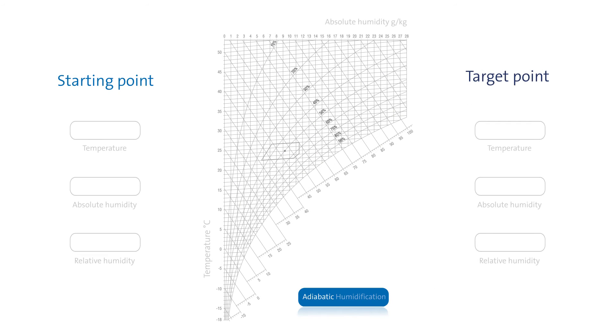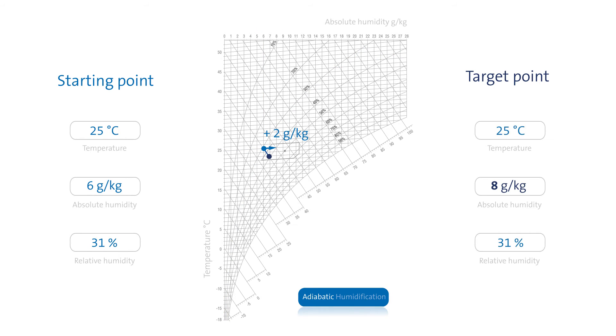An HX diagram can be used to illustrate this process. As a result, adiabatic humidification of 2 grams per kilogram of air causes air temperature to cool down by 5 degrees Celsius.